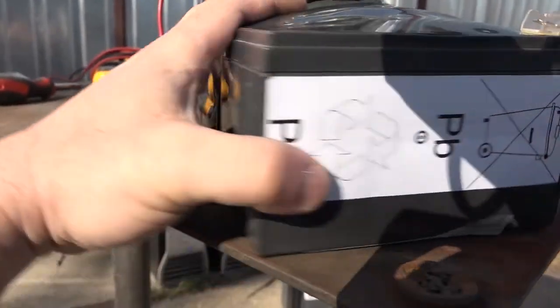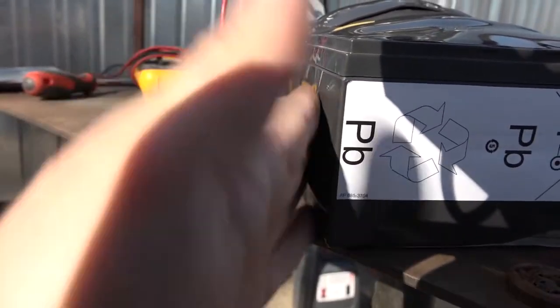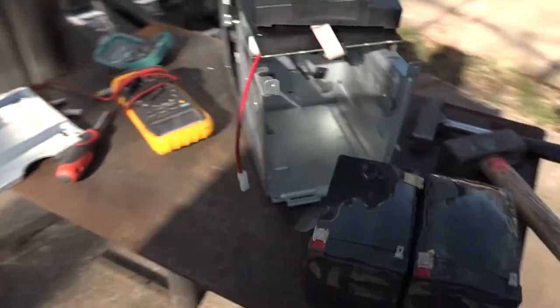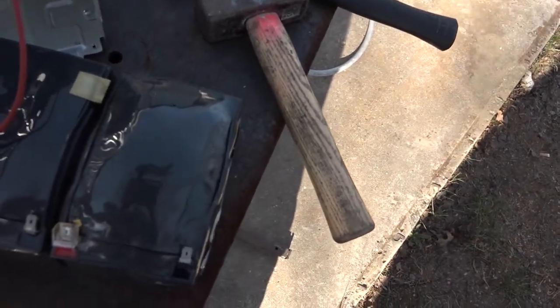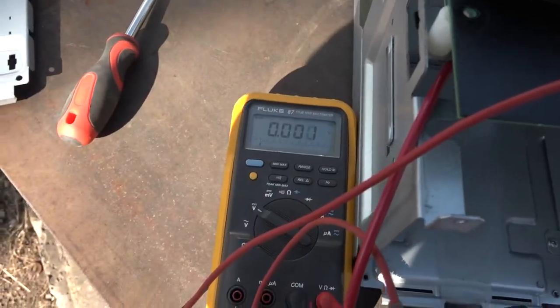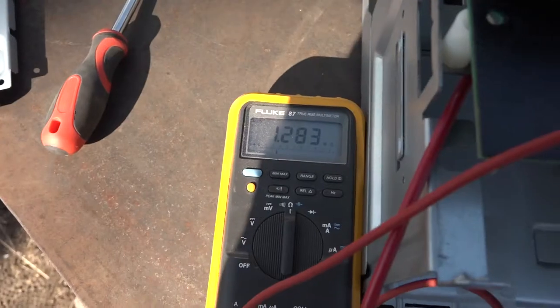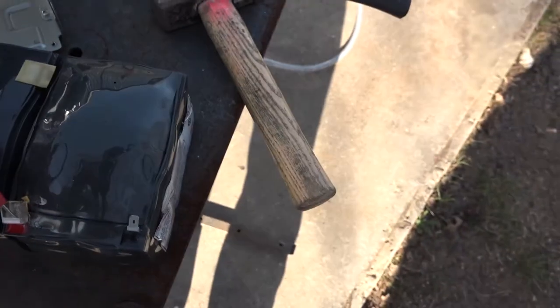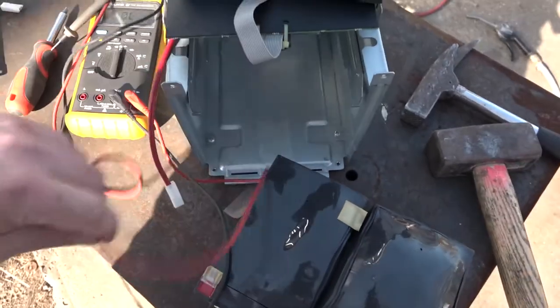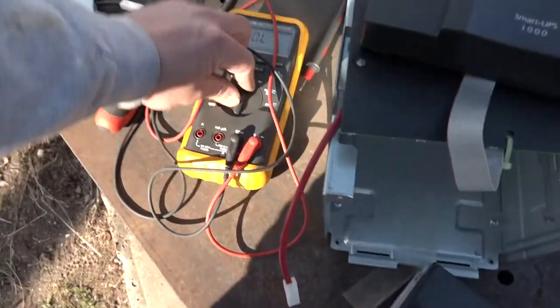You can see the level of damage here. This is really nasty. Let me do some measurements. This is the voltage we have in the accumulator — I'm not surprised at all. And let's check the other one — zero point nothing voltage. So let's check the resistance: 1.2 megaohm after the fault. And another one: 1.6 megaohm. I hope this data will help APC to redesign their products.